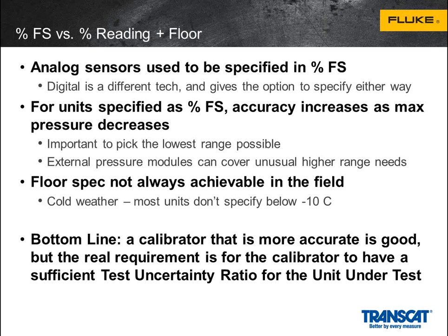floor spec. A great example of this is if you take the unit, and in a lab, there's no question that a unit will be able to achieve this floor spec. But if you just take it into your living room or your kitchen, you turn the unit on, place it on the table, hit the 0 button, and walk away. If you sit there, you can actually watch the 0 shift. And your living room is nowhere near as rugged as the field can be, and so it can be very, very hard to really achieve these values in the real world.